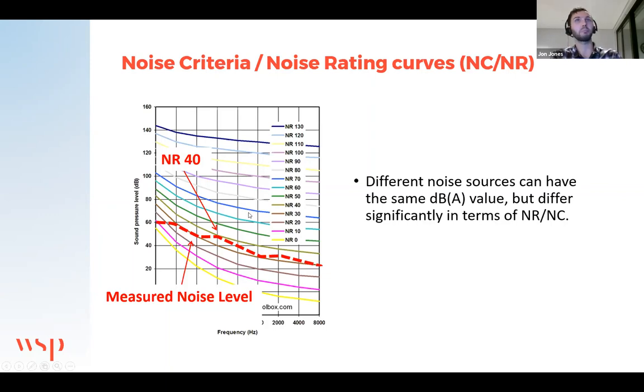So it's a bit of background there about NC curves, which you'll often see referenced against building services equipment as a noise level. Really, that's how you derive and compare. So a specific dB level is not necessarily comparable to an NC curve. That's the analysis that goes on behind the scenes to see what they equate to.